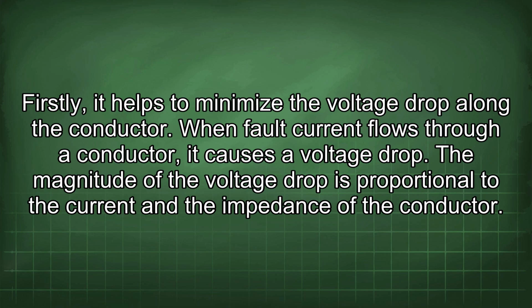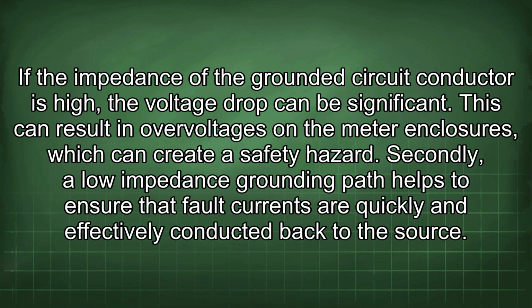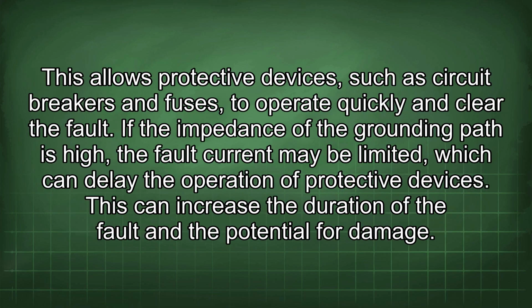The magnitude of the voltage drop is proportional to the current and the impedance of the conductor. If the impedance of the grounded circuit conductor is high, the voltage drop can be significant. This can result in overvoltages in the meter enclosures, which can create a safety hazard. Secondly, a low-impedance grounding path helps to ensure that fault currents are quickly and effectively conducted back to the source. This allows protective devices, such as circuit breakers and fuses, to operate quickly and clear the fault. If the impedance of the grounding path is high, the fault current may be limited, which can delay the operation of protective devices. This can increase the duration of the fault and the potential for damage.